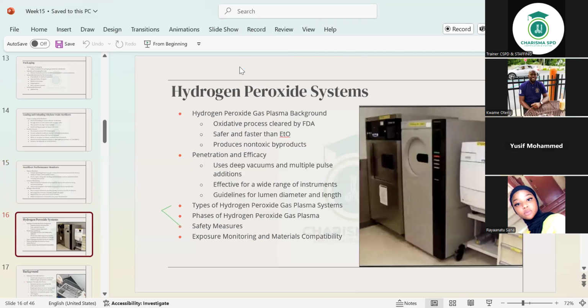Okay. So now the second one is the hydrogen peroxide systems. We said there were three, right? The ethylene oxide, hydrogen peroxide, and then the ozone. Okay, now we're doing the hydrogen peroxide. It's a gas plasma. The background is that oxidative process. We said the first one used what? Alkylation, whereby it attacks some proteins in the microorganism, cuts off their reproductive powers or strengths, and then overpowers them. By attacking those proteins, they're able to overpower the microorganism. That's the alkylation. Now we say that we are using hydrogen peroxide, and what it uses is oxidative process, which has been cleared by the FDA.